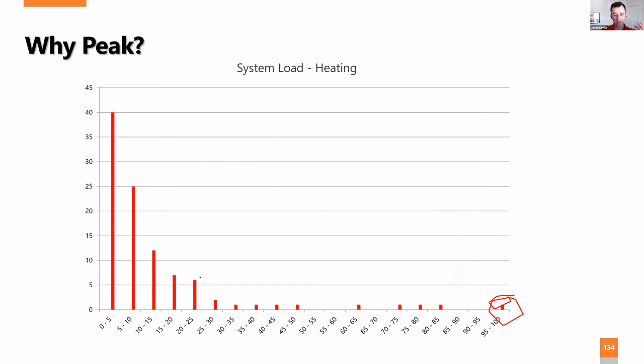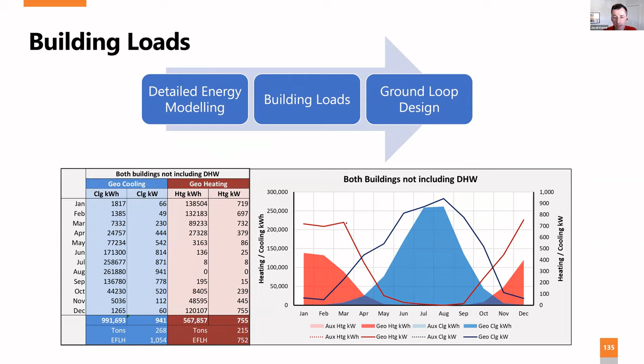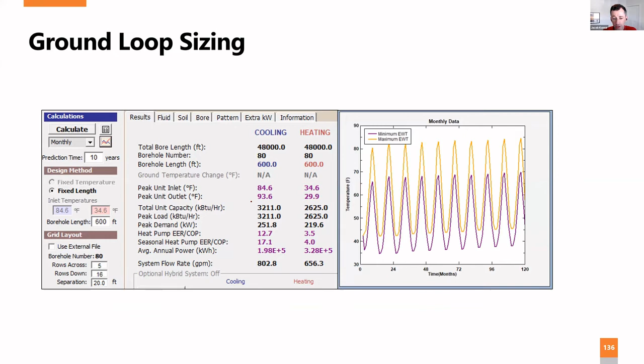So for geo, we need detailed energy modeling to get building loads, which gives us the heating cooling balance. And then we export that to our software and we size it using software. A lot of problems in the past with geosystems were because rules of thumb were used and they weren't engineered, and that can create a lot of problems. I've seen some really horrific geo designs. And so the loads matter.